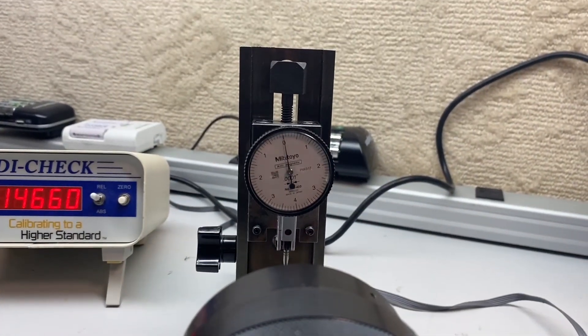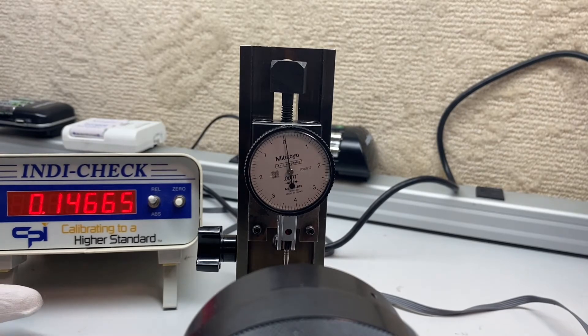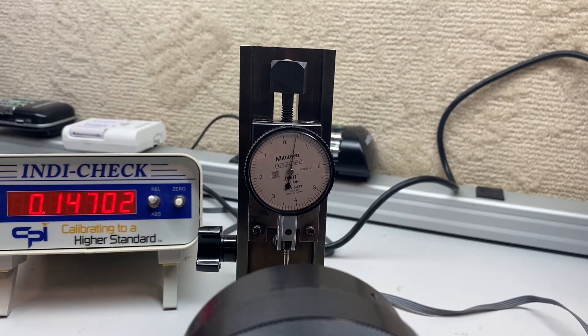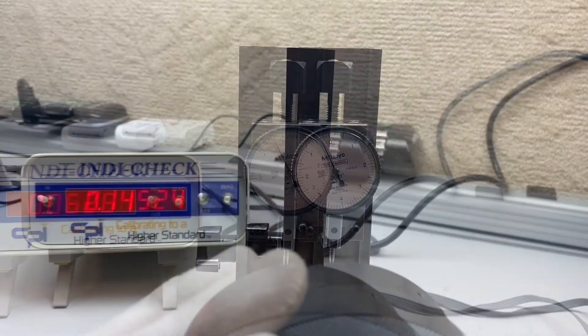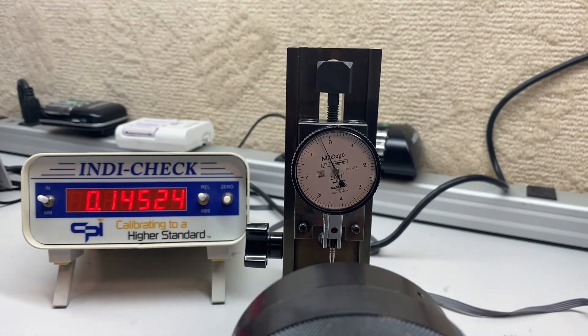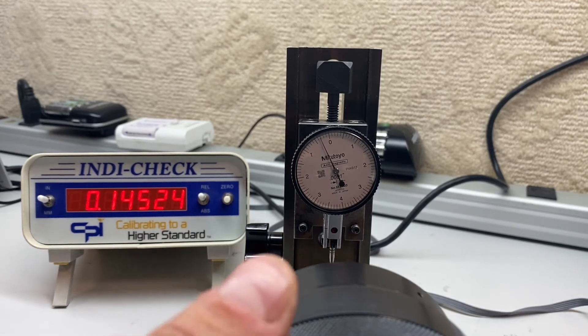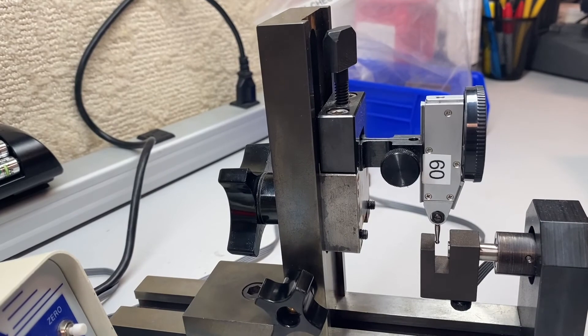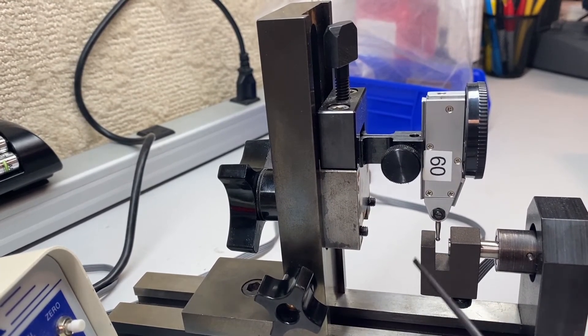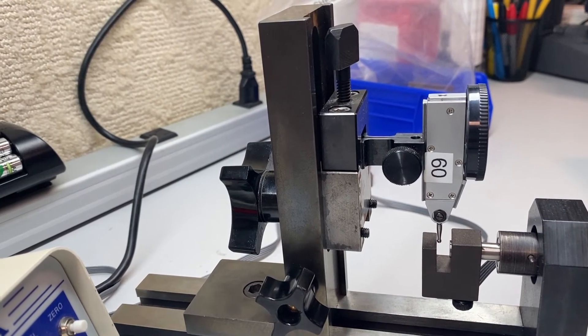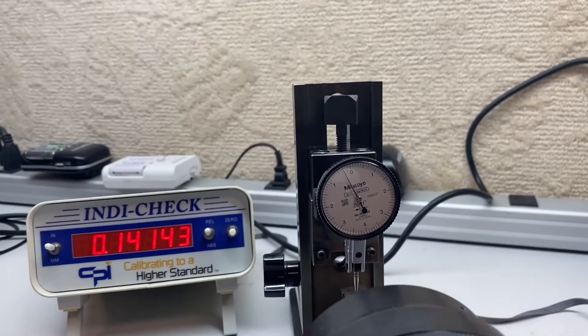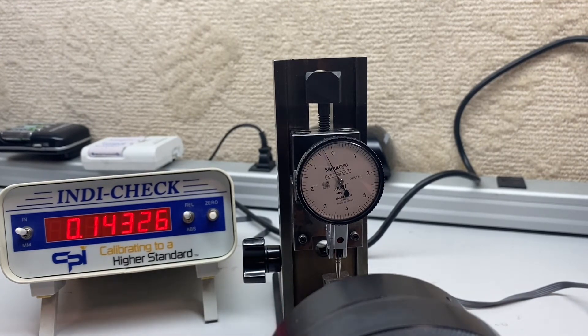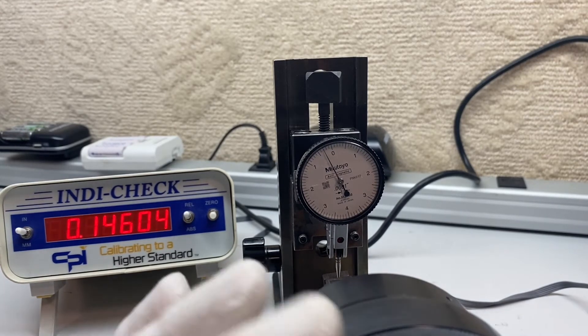All right. So a continuation of the other video. I'm going to continue to now test this test indicator, or calibrate the test indicator, by pulling it forward using the Indy check and its fixturing. Fixturing looks like this. So it is now pulling forward on this tab on the stem, pushing forward. So it comes off and comes forward. We're going to index forward and set zero. There we go.